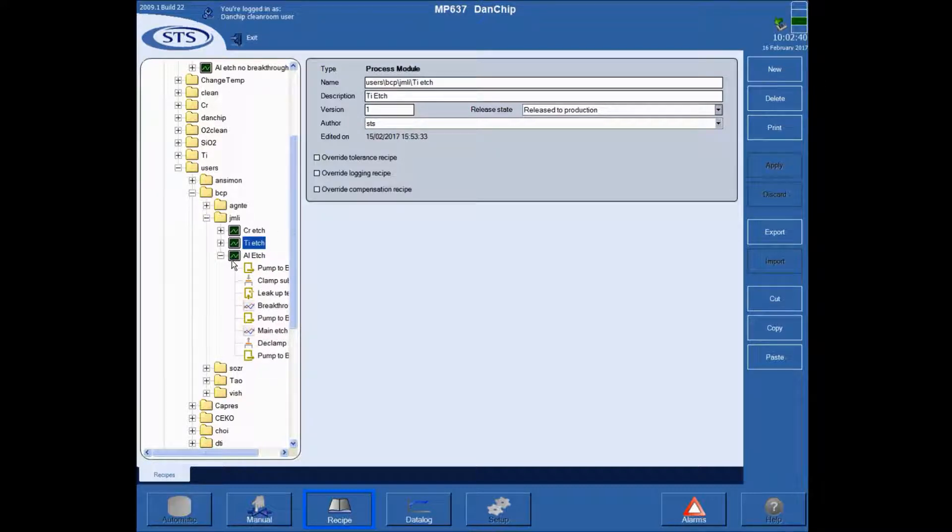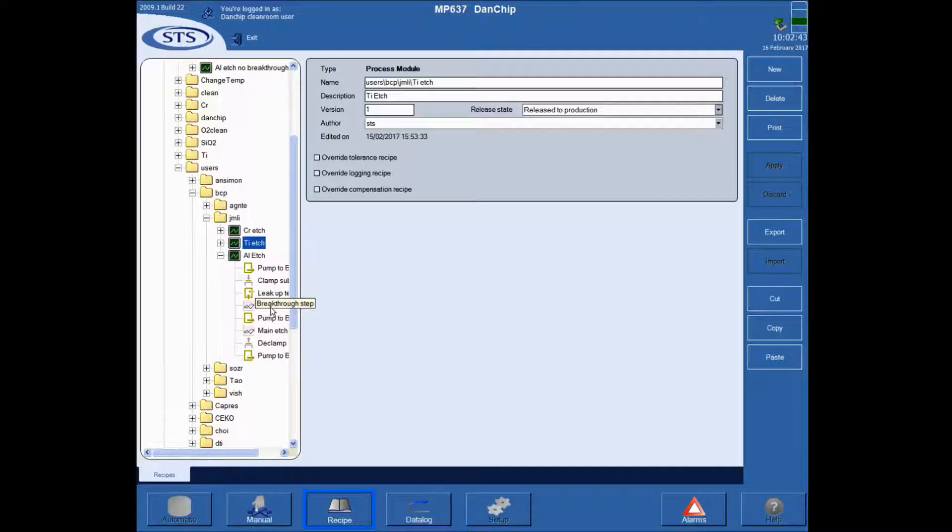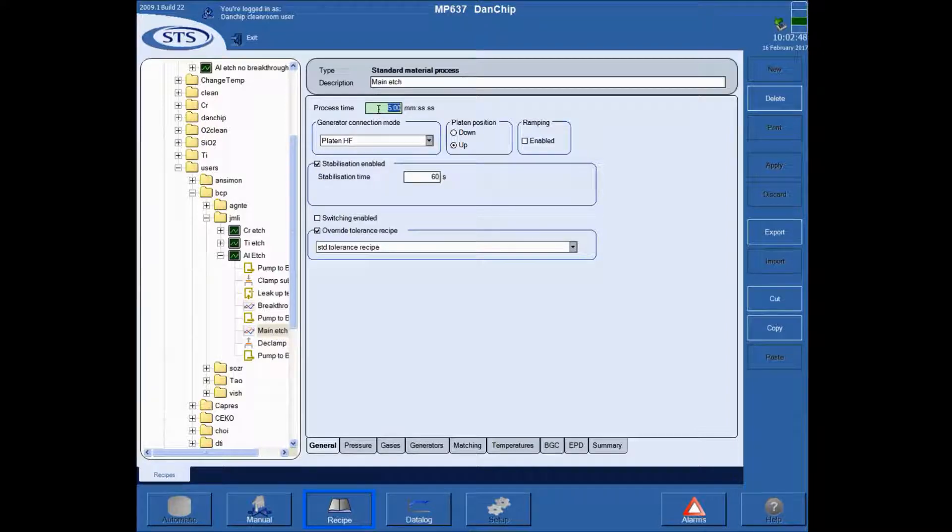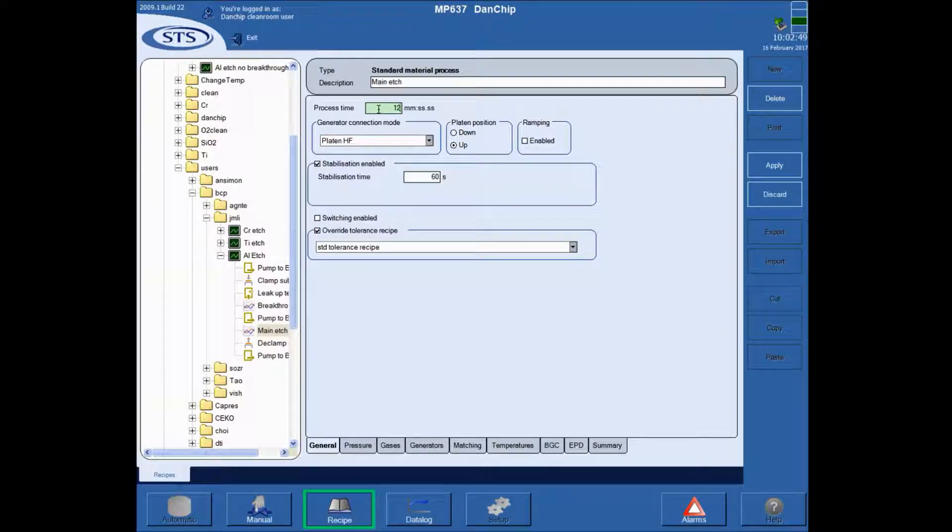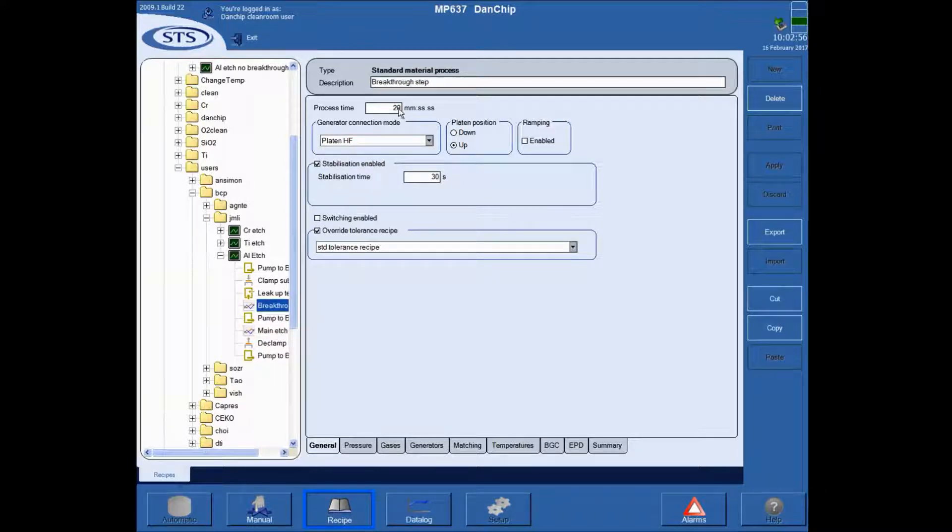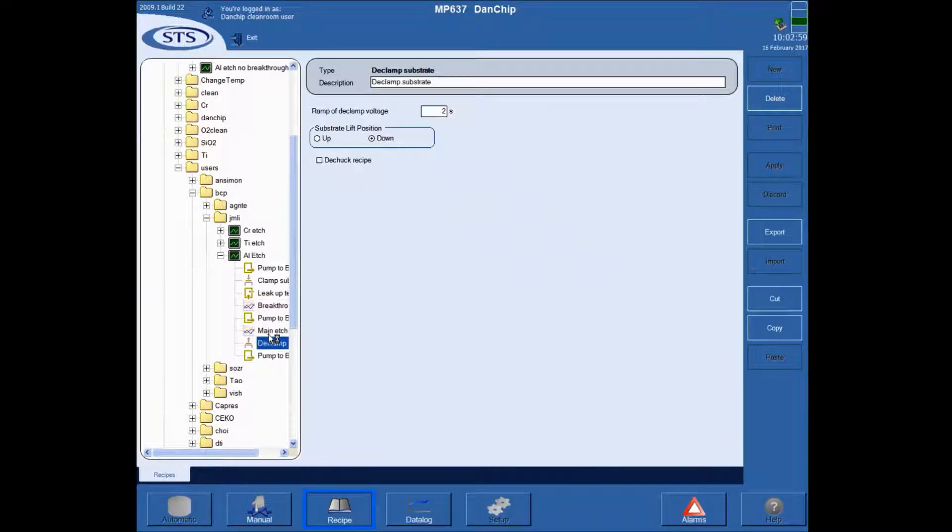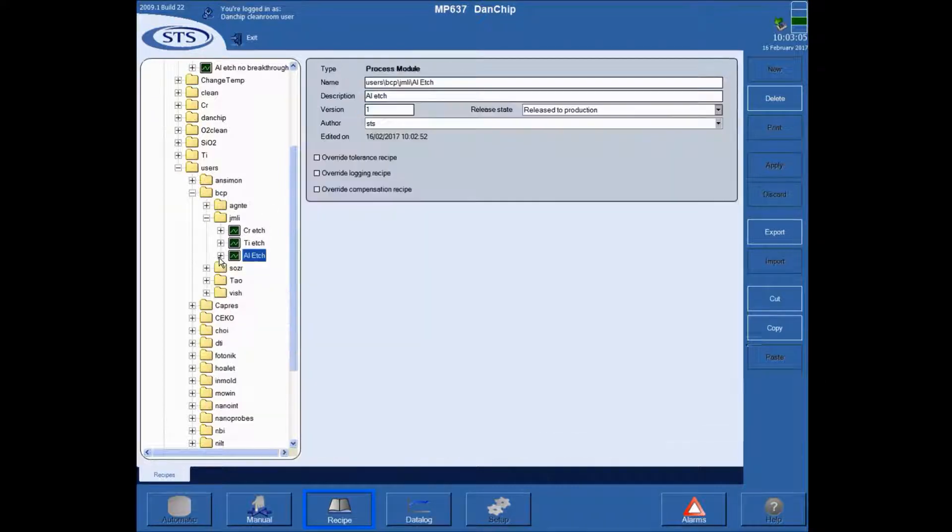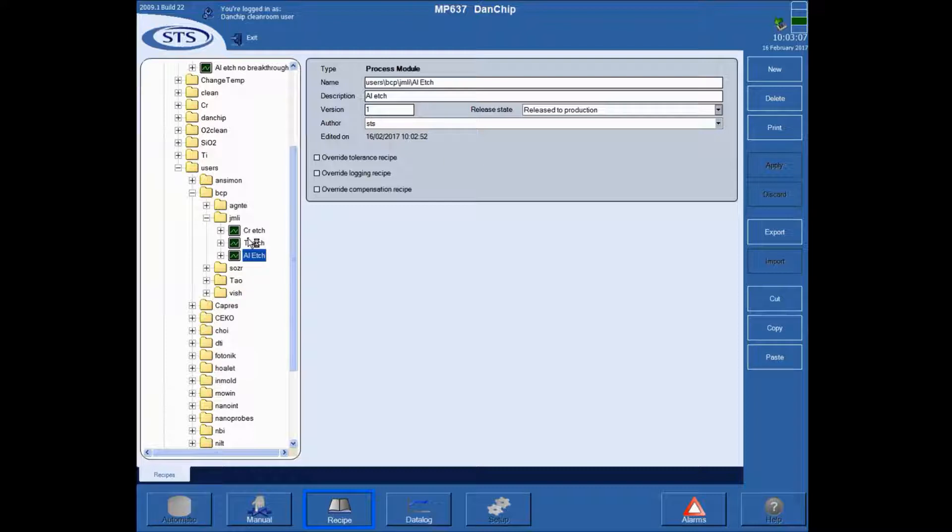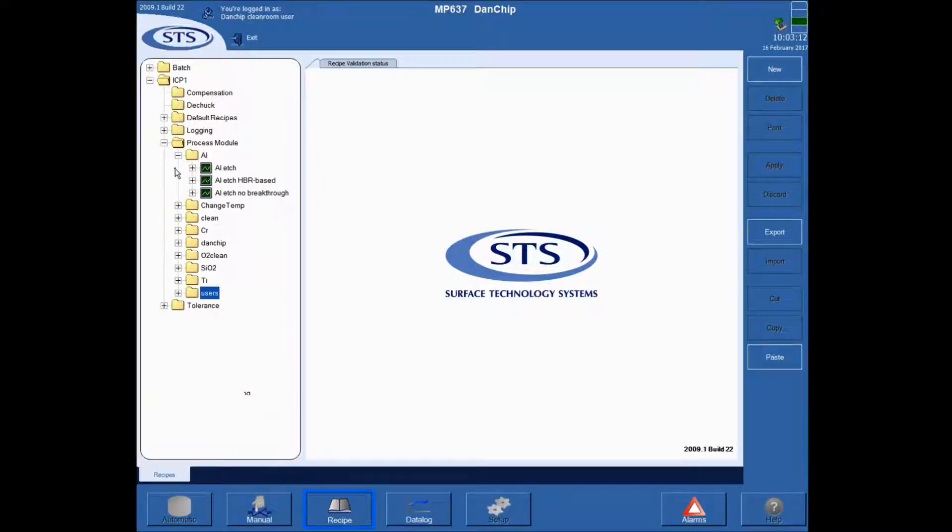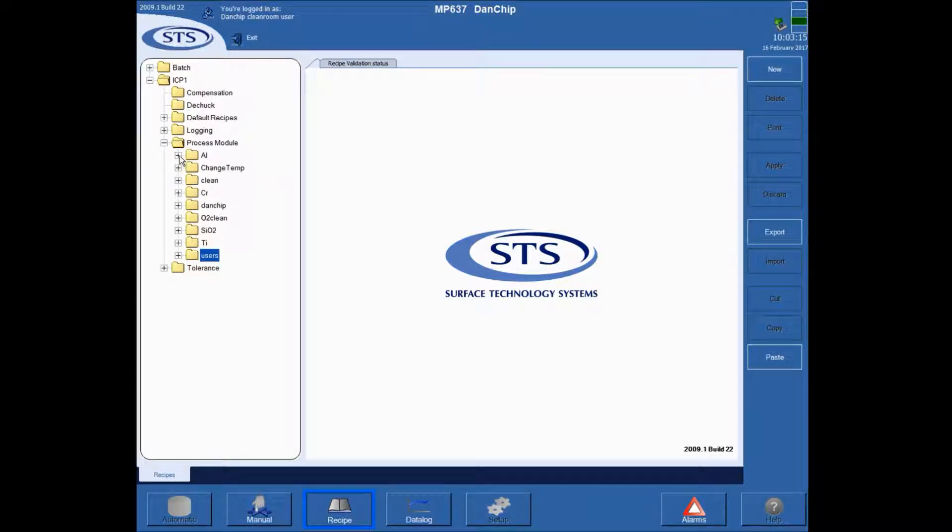So, in this way I have created my own recipe and I can modify it, if for instance I want to etch less time, 2 minutes. So, in total this will etch for 20 plus 2 minutes, 2 minutes and 20 seconds. So, that shows how you to work with recipes.